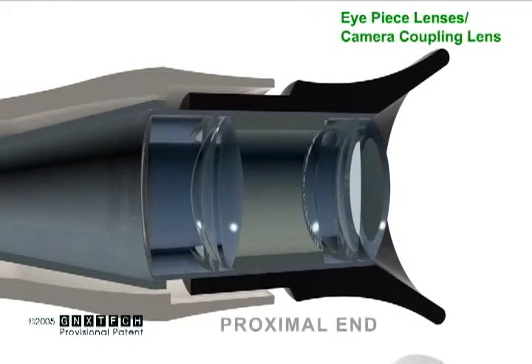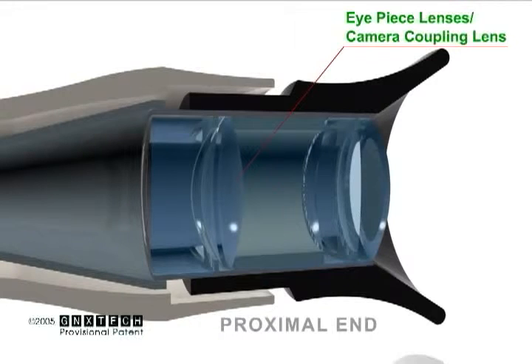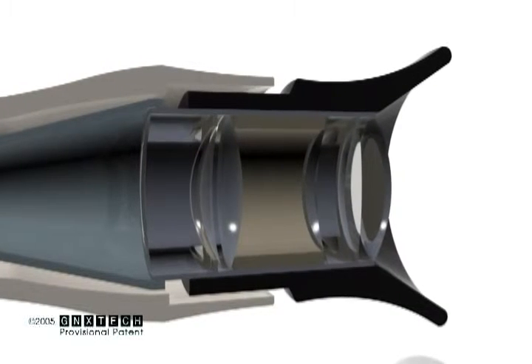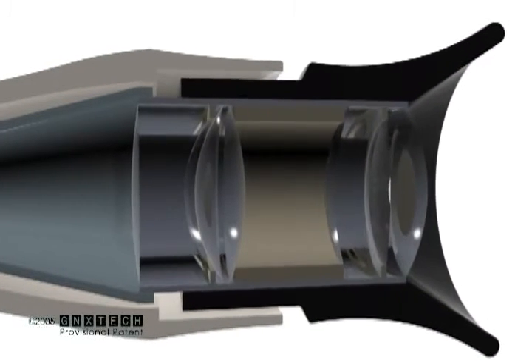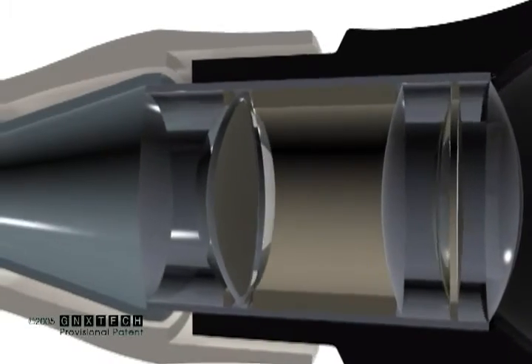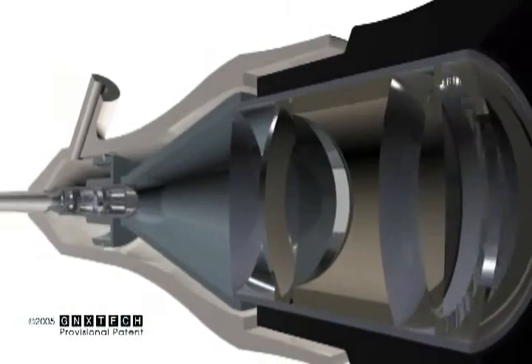Depending on operator option, an image may be either directly viewed or captured in a CCD camera. The eyepiece is quickly removed to allow placement of the camera and camera coupling lens. 7 power magnification in this stage provides an overall image magnification beyond 40 power for the overall endoscope. The eyepiece is by design very insensitive to misplacement, so it is readily maintained in focus. It will be possible later to add dioptric correction for surgeons who need visual correction.